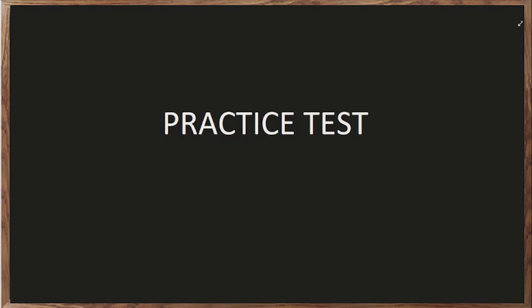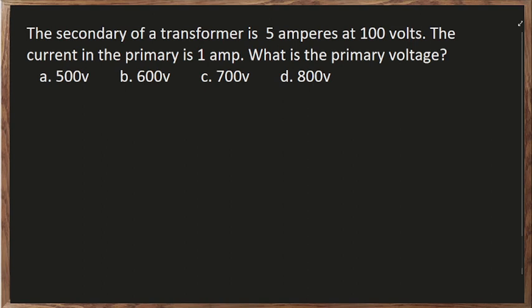Okay, so we have number one. The secondary of a transformer is 5 amperes at 100 volts. Now the current in the primary is 1 ampere. So what is the primary voltage? Okay, so we have here our solution. When we say transformer ratio, the transformer ratio is the voltage of the primary over the voltage of the secondary, equal to the number of turns on the primary over the number of turns on the secondary, equal to the secondary current over the primary current.